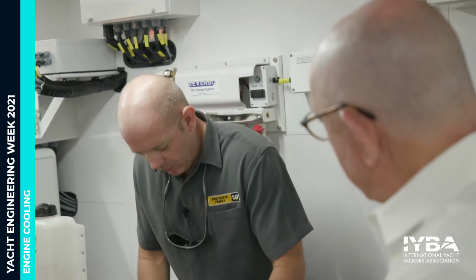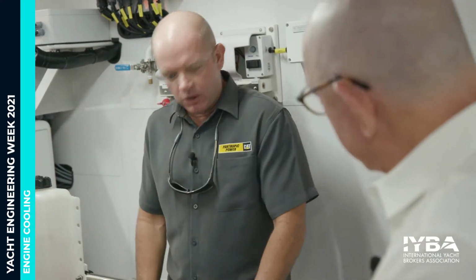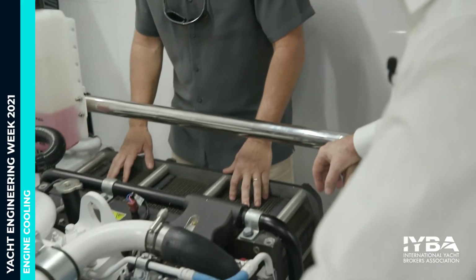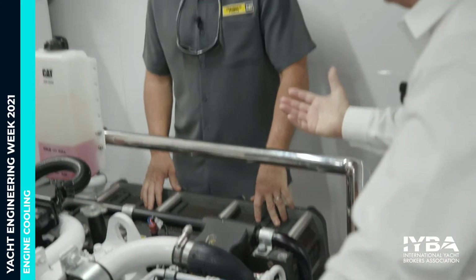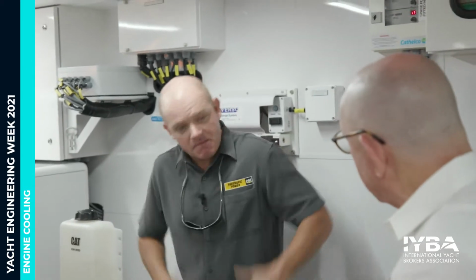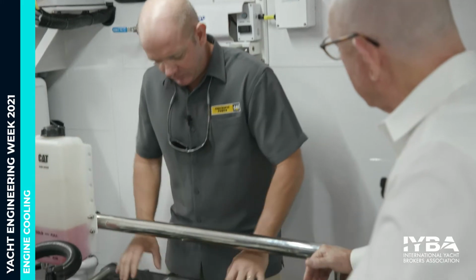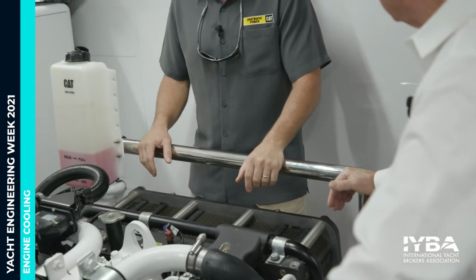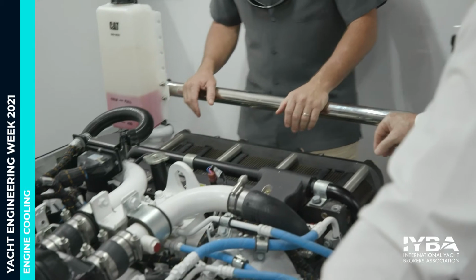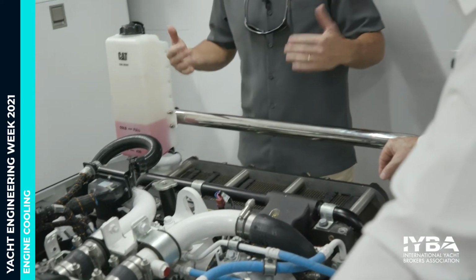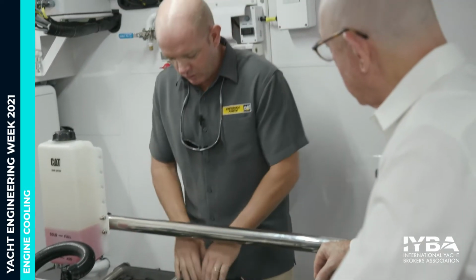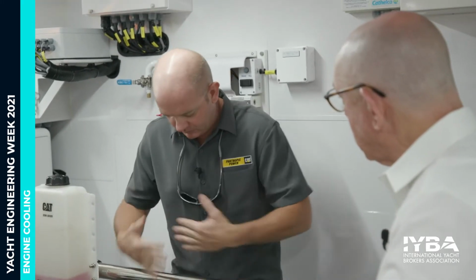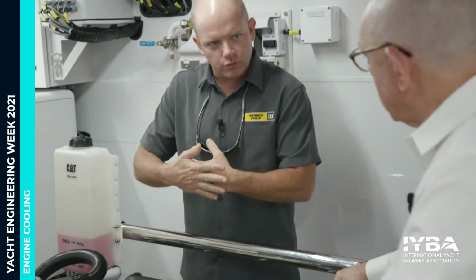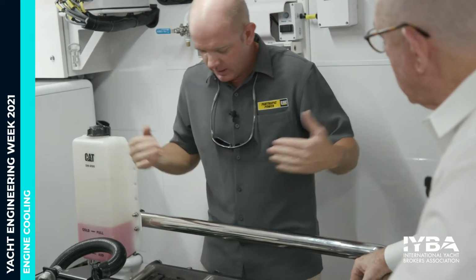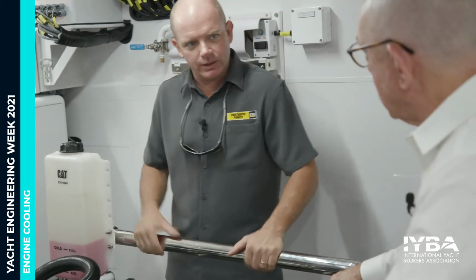That's why these titanium plate types are becoming the standard. Titanium is a space age metal, and an expensive one in theory, but it's actually pretty common. It's highly corrosion resistant, which is important in a saltwater environment, and it also rejects heat very well. So it's great for this system, where seawater goes one direction and coolant the other, pulling the heat out of that coolant as it goes by.